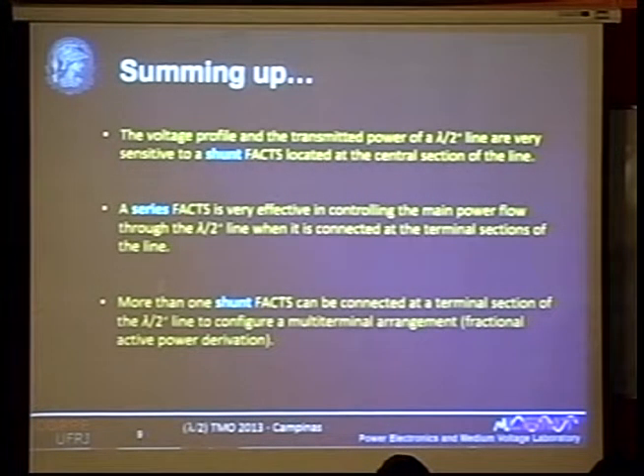So as not to spend too much time analyzing graphs, there are three points to emphasize. The voltage profile and transmitted power of the slightly-more-than-half-wavelength line is very sensitive, with a very high correlation, to a FACTS shunt located in the central section of the line. A series FACTS is much more effective in controlling the main power flow when connected in the terminal sections of the line, both at the emission and receiving ends.